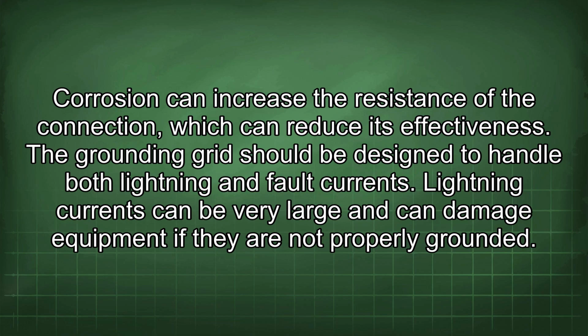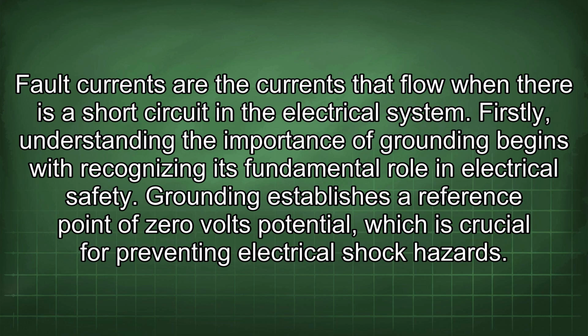The grounding grid should be designed to handle both lightning and fault currents. Lightning currents can be very large and can damage equipment if they are not properly grounded. Fault currents are the currents that flow when there is a short circuit in the electrical system.